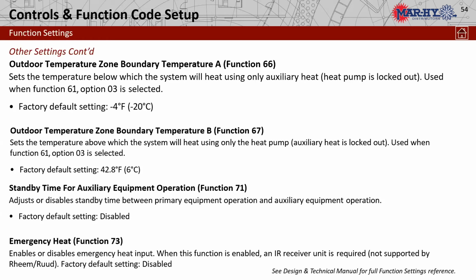The zone boundary temperature B, function 67, this is actually our heat strip lockout. This is where we will set the lockout of the strip heat to a minimum temperature. There again, I've got those settings on our startup guide. Basically, 6 is 32, 7 is 35. So I gave you 2 options. Pick what you like, and that'll keep the heat strip locked out till we make our minimum outdoor temperature, or lower than our minimum temp.